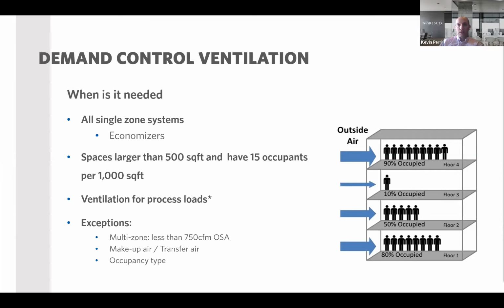So let's flash back into the 2021 code cycle. Demand control ventilation, when is it needed according to this code cycle? So all single zone systems that have an economizer, remember that section on economizers that we talked about previously, quite a few systems were required. If it's a single zone system and it has an economizer, they are now required to have demand control ventilation.